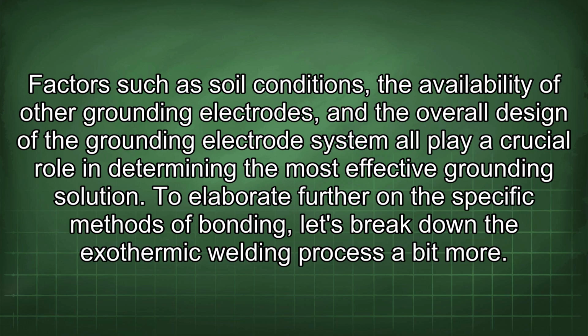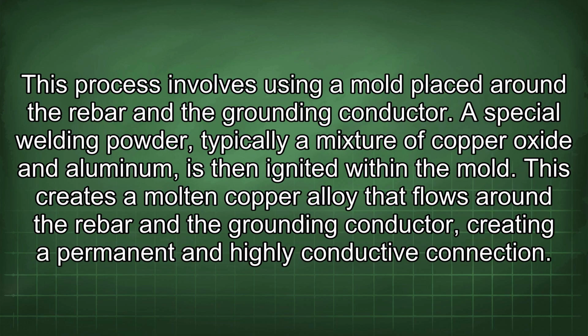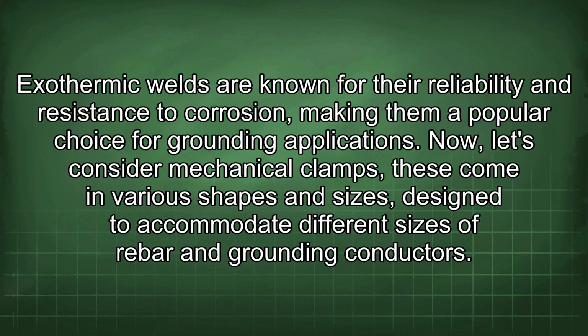To elaborate further on the specific methods of bonding, let's break down the exothermic welding process a bit more. This process involves using a mold placed around the rebar and the grounding conductor. A special welding powder, typically a mixture of copper oxide and aluminum, is then ignited within the mold. This creates a molten copper alloy that flows around the rebar and the grounding conductor, creating a permanent and highly conductive connection. Exothermic welds are known for their reliability and resistance to corrosion, making them a popular choice for grounding applications.